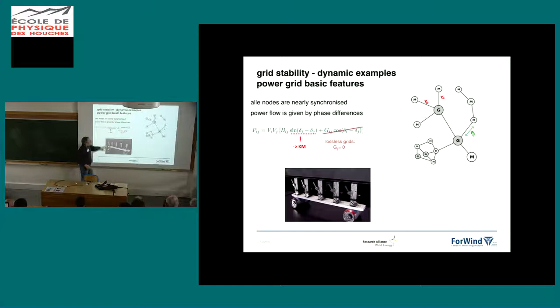Then they are synchronized, but they do not have to be in phase, at the same angle. One can run with the angle a little bit ahead. If you have an angle difference between two points, this tells you the power flow. If one is ahead, it's as if they're connected by a spring: if one is ahead, it is always pulling the other one behind; if it's behind, it is pushing. This is just the same with a generator: if it's ahead in phase, it's putting energy in; if it's behind, it's pulling energy out. This is the difference between a generator and a motor. So these phase differences between points determine the power flow.